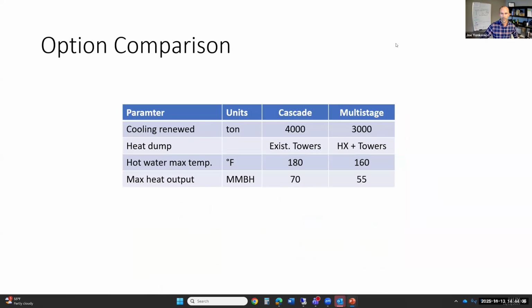Comparing the Cascade option with the multi-stage, these are some of the numbers the vendors put in front of us. With Cascade, we'd be able to renew 4,000 tons of cooling, that was our goal. With the multi-stage, because of the size of machines and because of cost, we just couldn't quite get there. The heat dump, when you have excess heat available in summer, was a big factor. The Cascade can use cooling towers at a much lower energy penalty. The multi-stage, because it doesn't have that double bundle, means putting tower water through heat exchangers, or using very large shell and tube heat exchangers. It just wasn't really palatable.